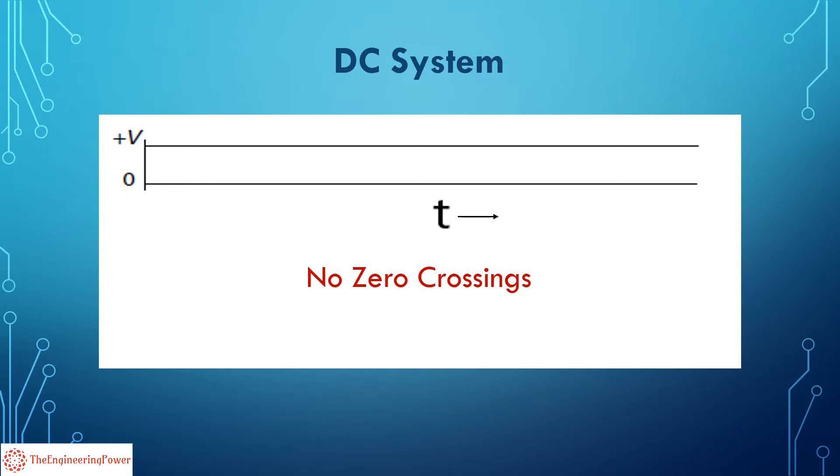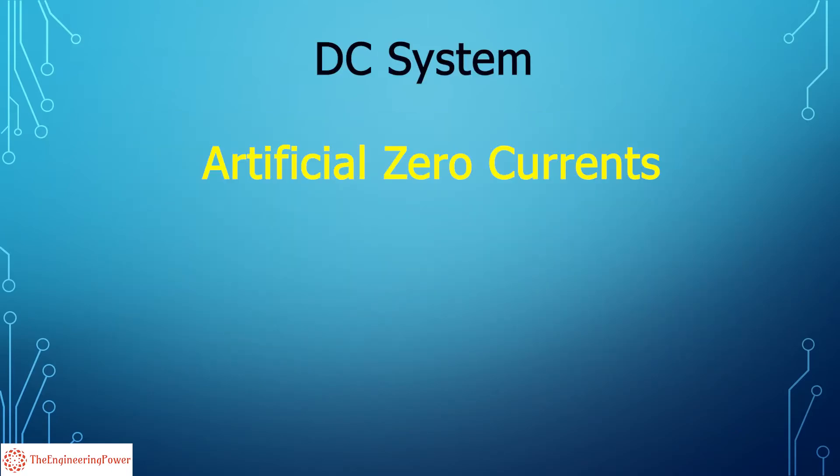So in order to extinguish the arc, artificial zero currents are introduced in the system using particular circuitry. So the HVDC breaker modeling is very complex as compared to HVAC breaker. Hence, the cost of HVDC breaker is very high as compared to the HVAC breaker.